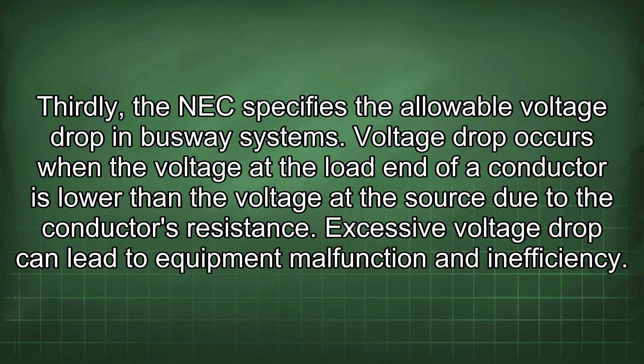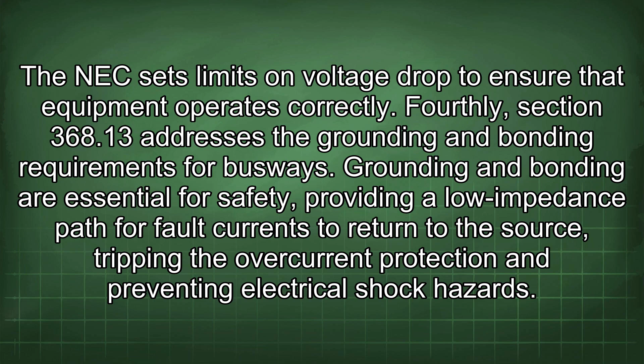Fourthly, section 368.13 addresses the grounding and bonding requirements for busways. Grounding and bonding are essential for safety, providing a low impedance path for fault currents to return to the source, tripping the overcurrent protection and preventing electrical shock hazards. The NEC mandates that busways be properly grounded and bonded to ensure electrical safety.